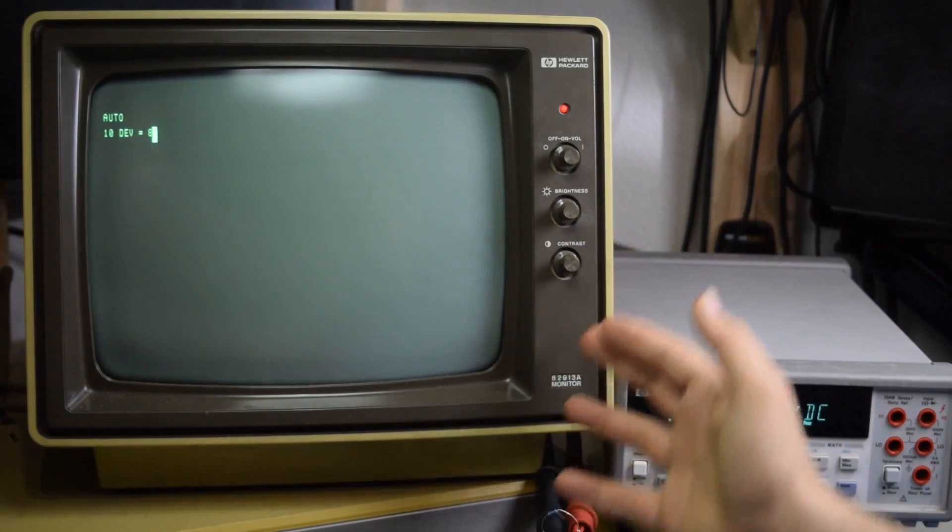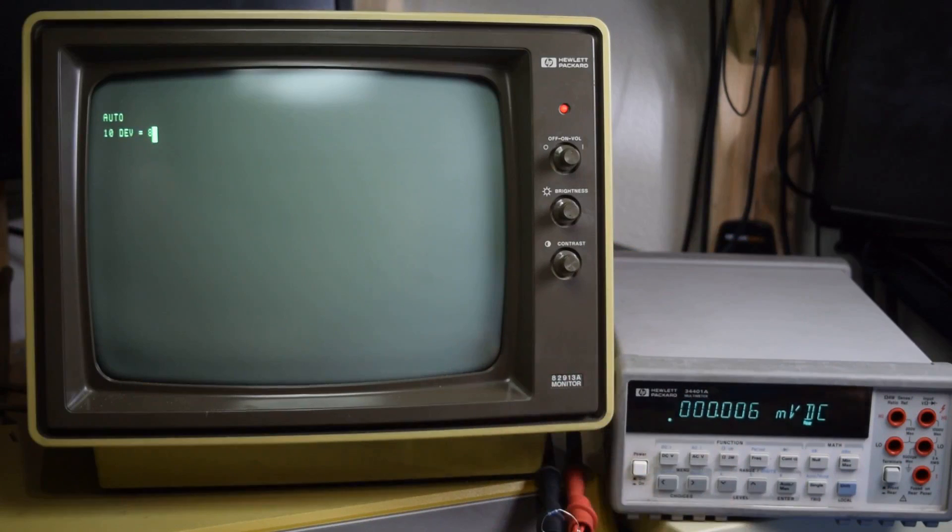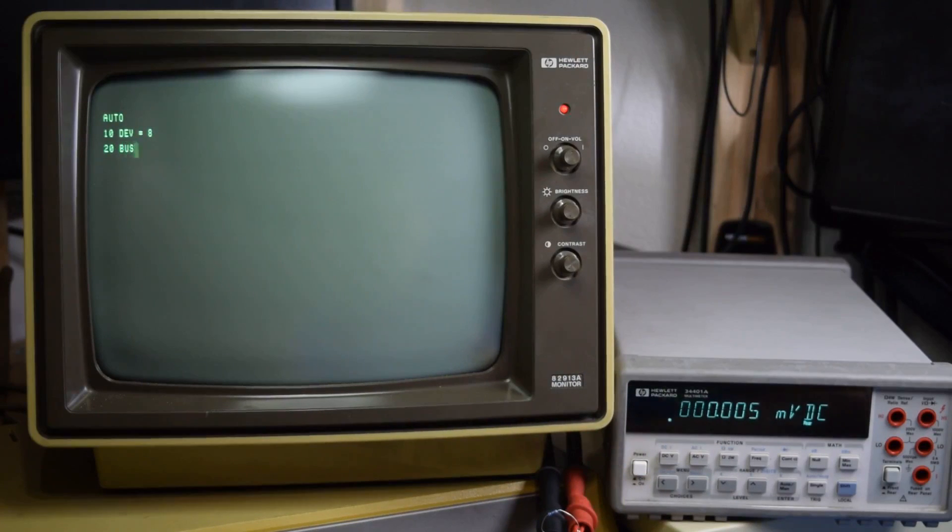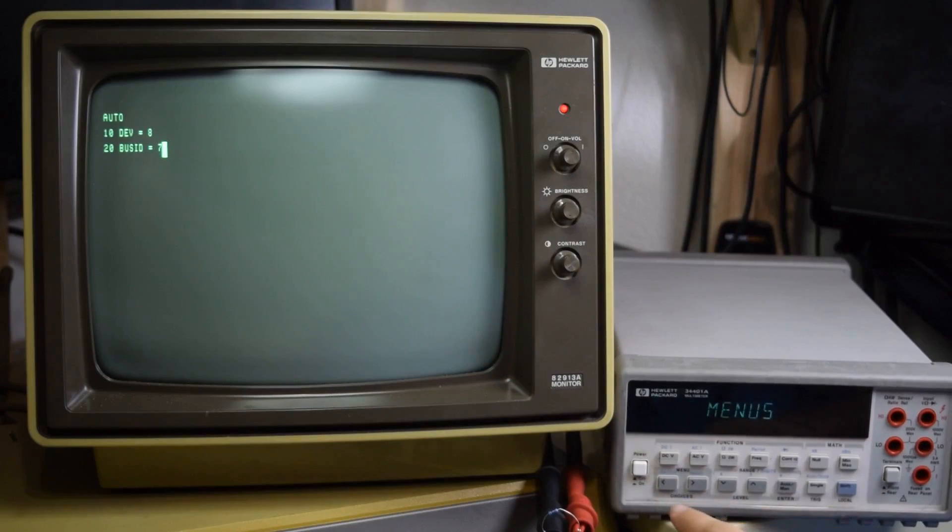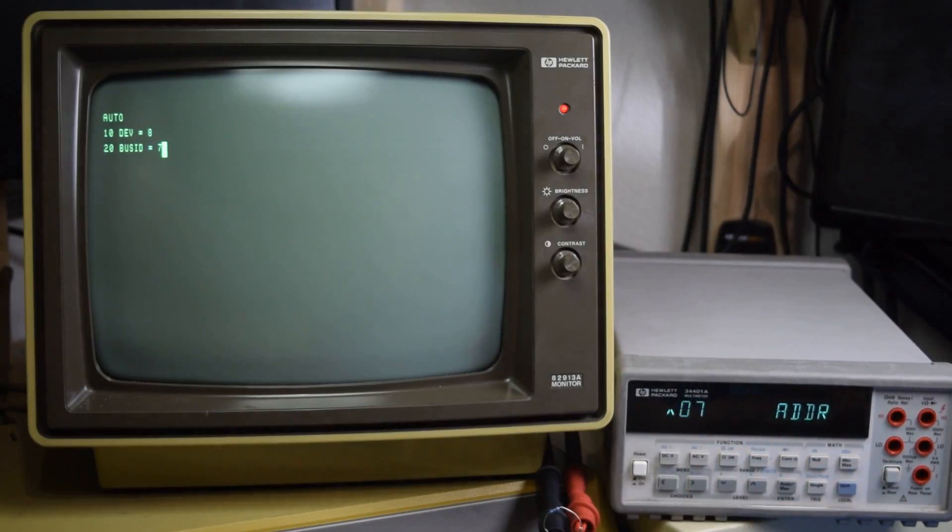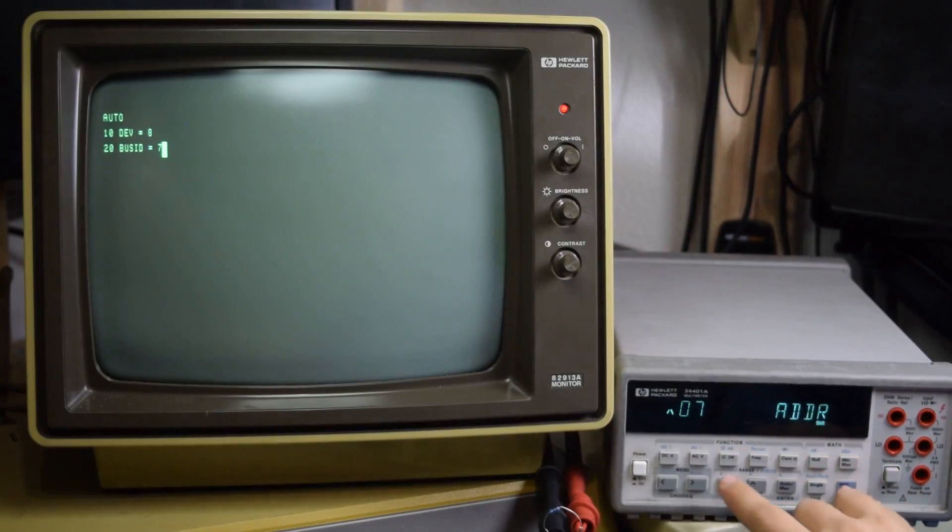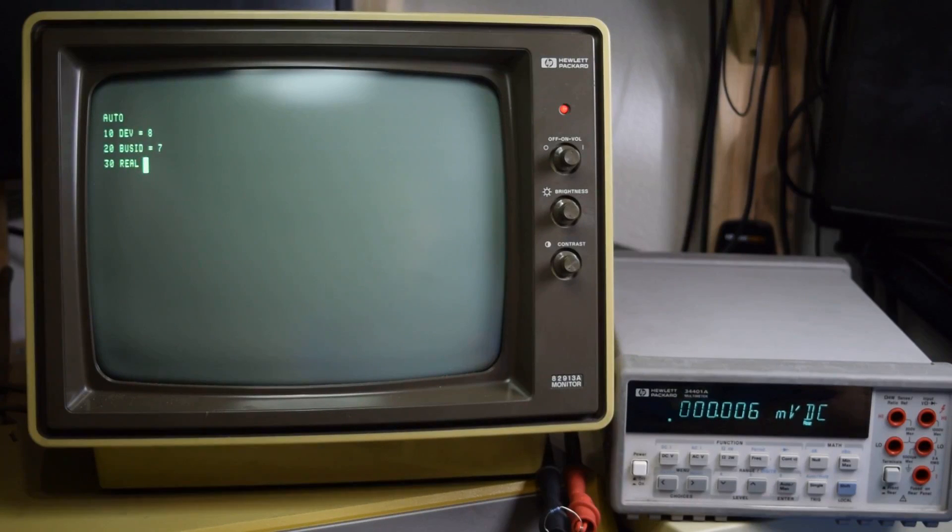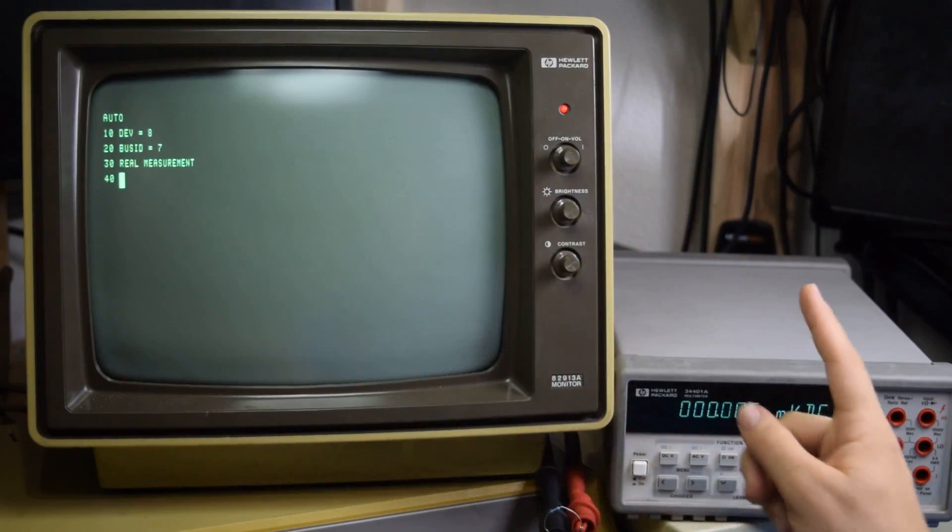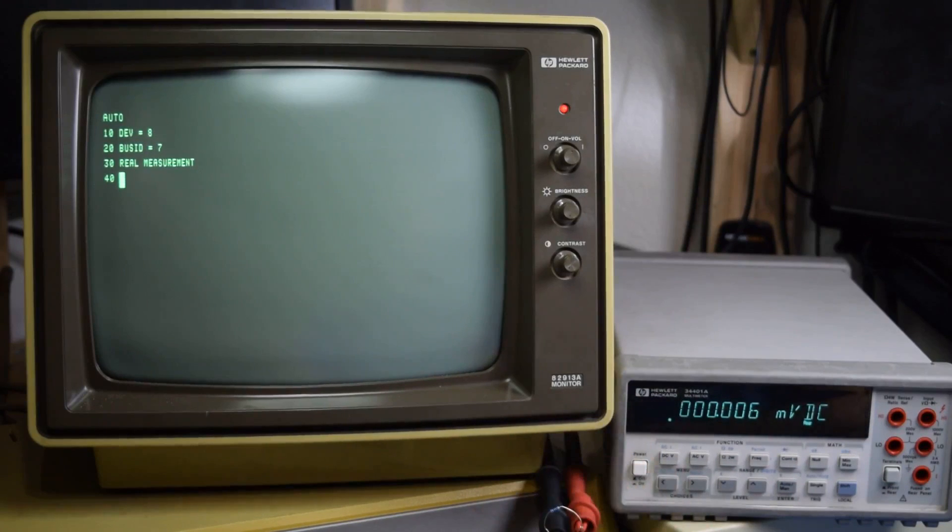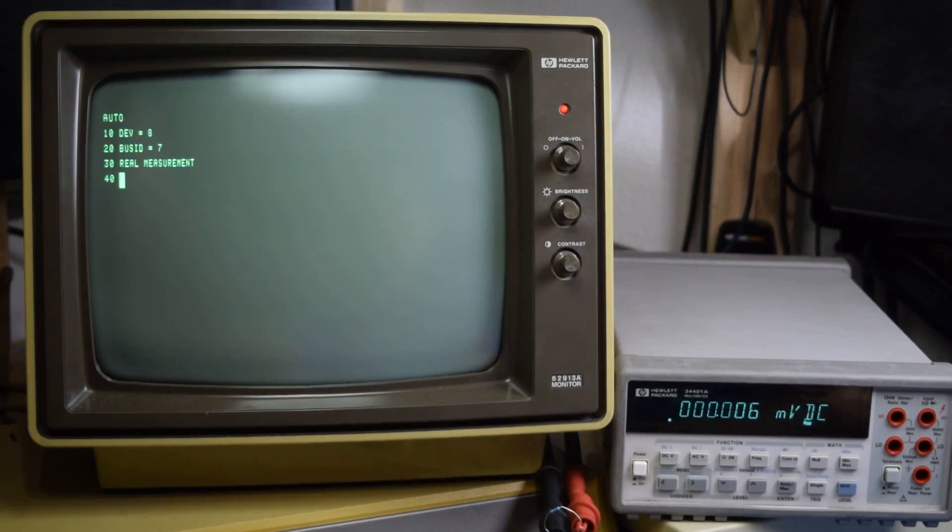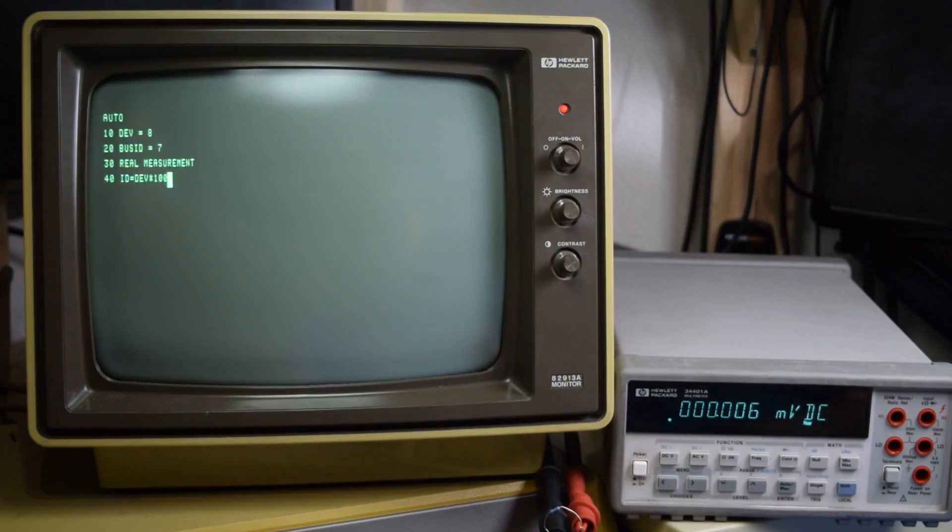The monitor, two disk drives, and the printer also all count as separate buses, so you need to define which one you're looking at. Next we're going to have a bus ID value that will be the ID of the multimeter on the GPIB bus, and we can see this by going into the menu on the multimeter and seeing what the address is. On this one it is 7. Now we're also going to create a real variable that will hold the measurement that we take. It needs to be a real because of the format that the multimeter returns the variable as. Next we need to create a three-digit number that represents the device ID and the bus ID. So we're going to create ID equals device times 100 plus bus ID.